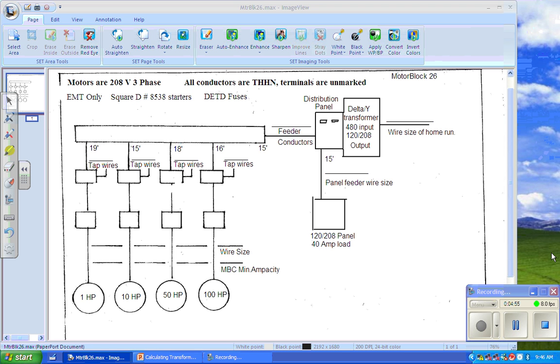And then B is generally for where you're just wiring inside the control cabinet, and that's not too big of a concern either. So column C is really where we're going to live, as it were. And I want you to look at where they extend beyond the enclosure, which is generally the case because you're going to have start-stop stations other places. You're going to have jog stations other places, not in the control cabinet door. Okay, now let's look at that column. Hang on.